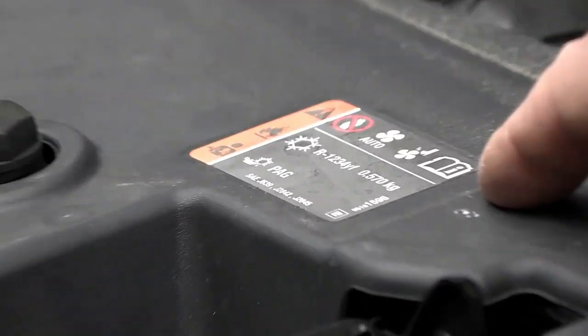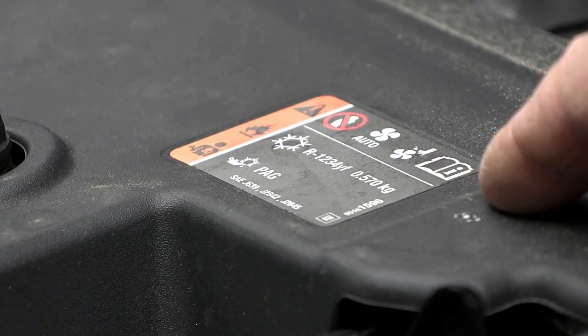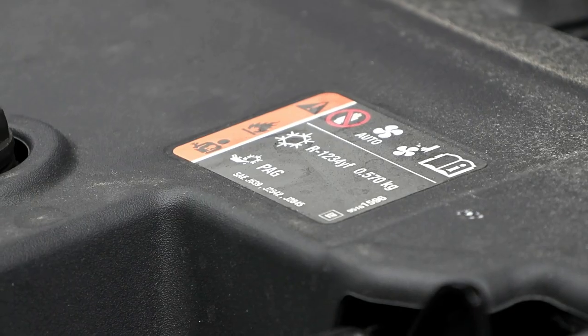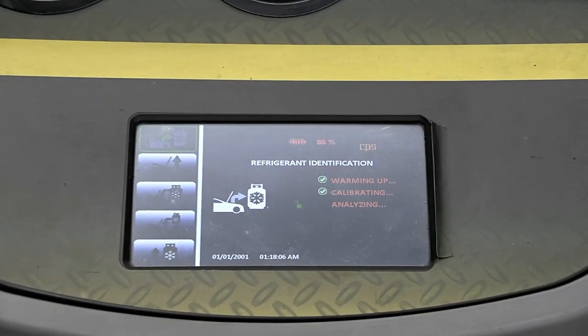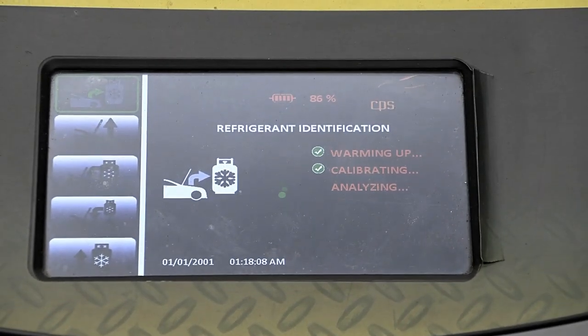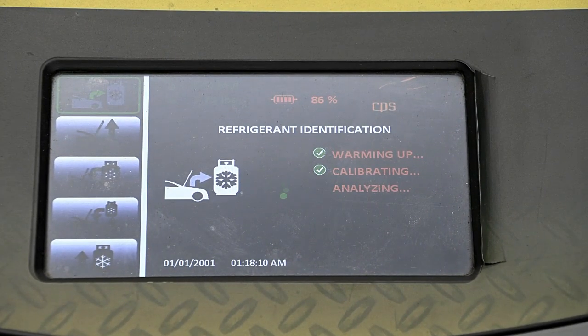We can change it from pounds to kilograms. We can change it to charge from the high side or the low side. We'll charge from both sides, and then we will shut the high side off. It'll tell you to do that to suck the last amount of refrigerant in.